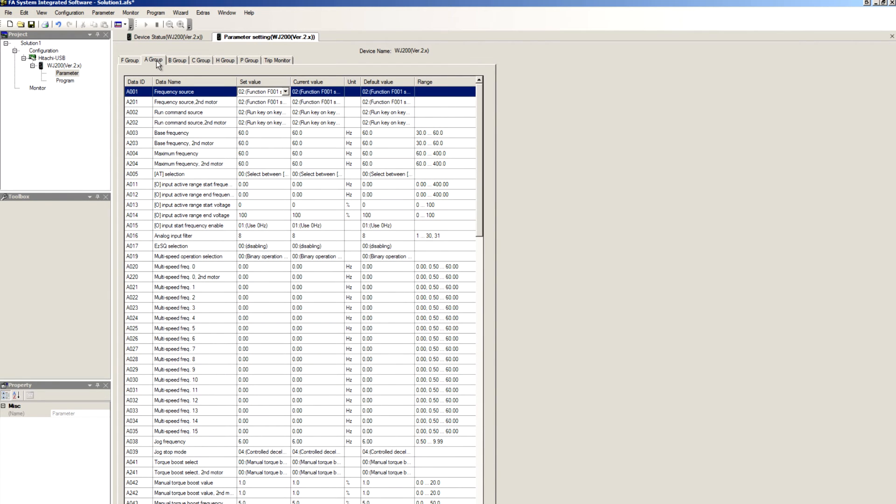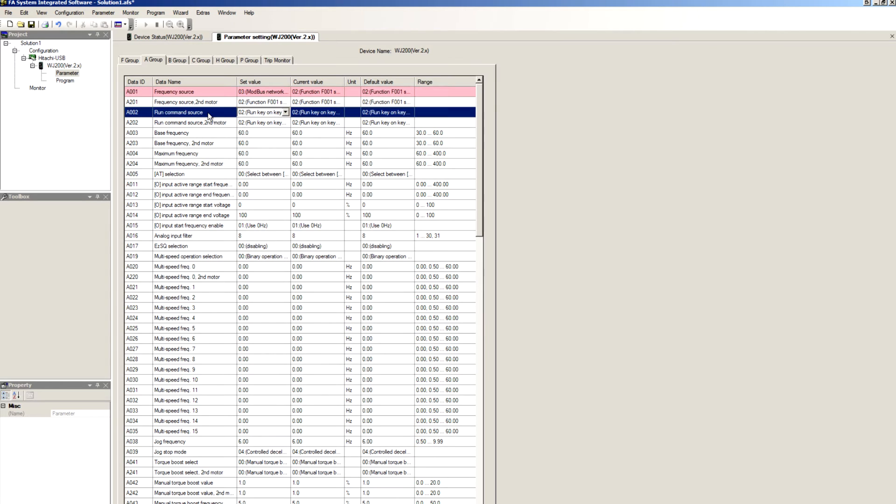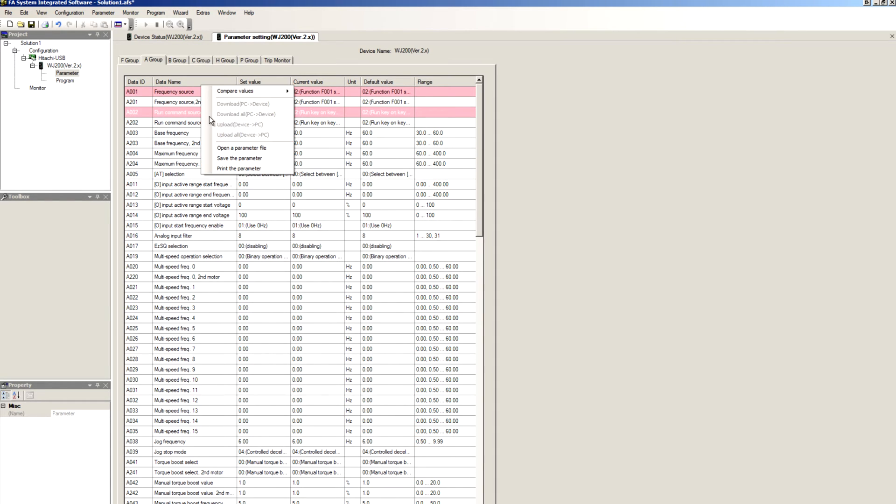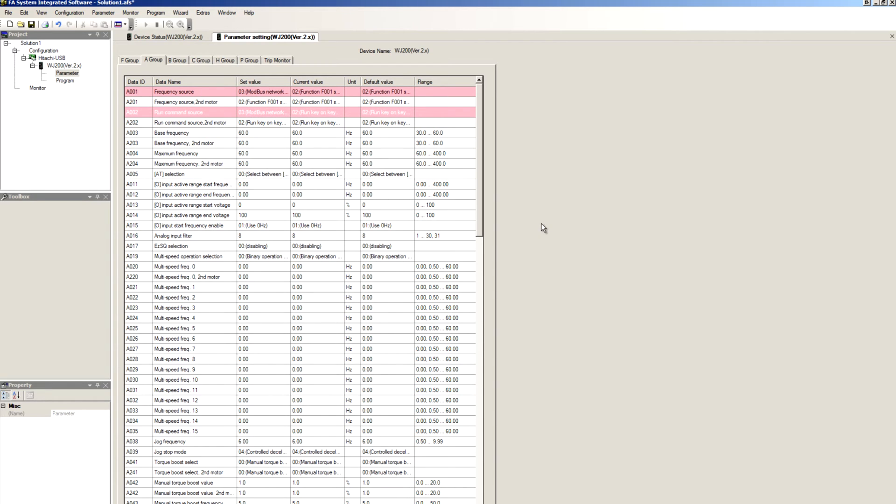Then in group A, make sure that we set our frequency source to Modbus Network, and run source to Modbus Network. Right-click, download all PC to device, and when it prompts you, select yes to save to EEPROM.